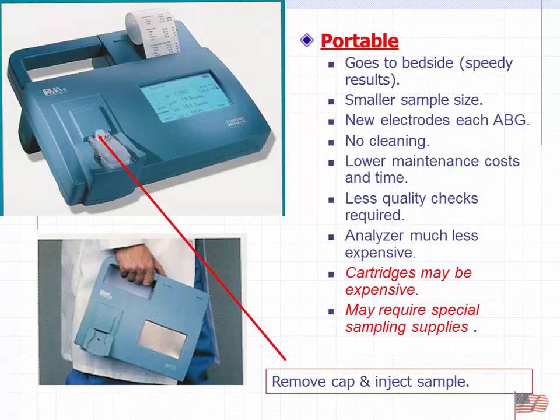On the other hand is a portable unit, where we can carry it to the patient's bedside, just like a glucometer or any other measuring device, and I can go ahead and get my blood gas readings. There's a smaller sample size, which is convenient, so we can do both arterial and capillary. Unlike the benchtop, every time we do a blood gas, we use a new little cartridge, and that cartridge has all of the calibration material as well as the electrodes themselves. So we do a blood gas, we take that cartridge and we throw it away. Awesome. So there's no cleaning, there's no maintenance, there's no quality control in the same fashion. The analyzer itself is a lot less expensive, but they get you on the cartridges. So it's kind of like here's a free razor, but you've got to buy the razor blades. They get you back on it.